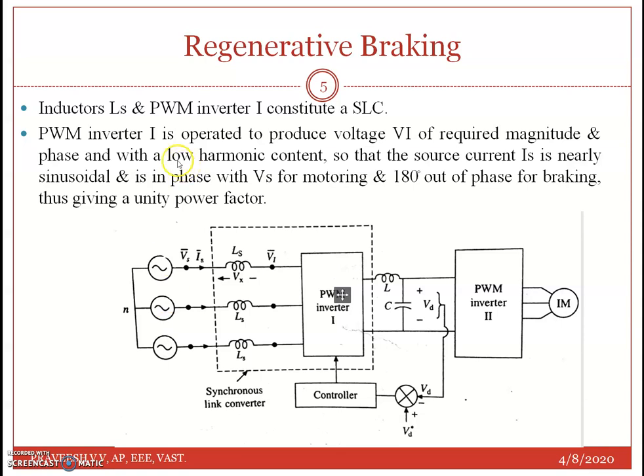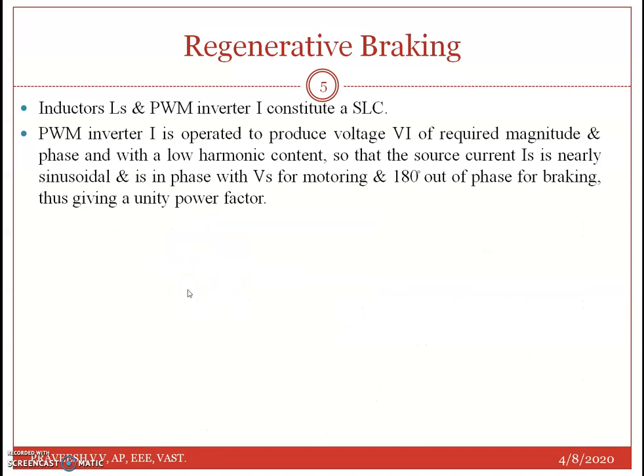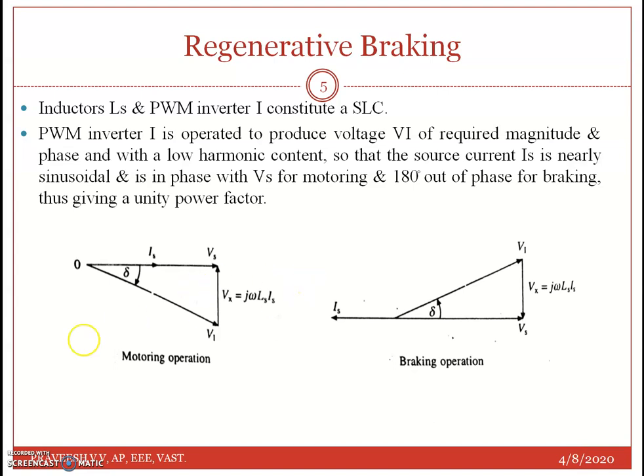In the synchronous link converter, PWM inverter 1 is operated to produce VI of required magnitude and phase with low harmonic content, so that the source current IS is nearly sinusoidal and is in phase with VS for motoring and 180 degrees out of phase for braking.